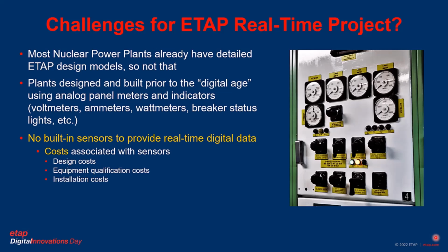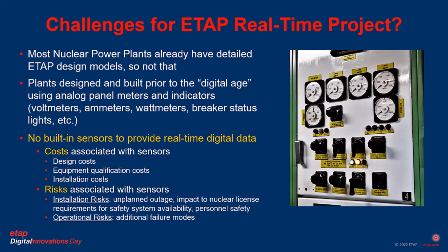There's design costs for sure, but there's also equipment qualification costs because in my industry, the equipment would have to be qualified to be installed. And then installation costs in my industry tend to be quite a bit more than in other industries. There's also risks associated with putting in the sensors that we need. For sure, there's installation risks, things like having unplanned outages. There could be impacts to the nuclear license requirements for safety system availability, and there could also be personnel safety issues, such as perhaps creating an arc flash likely situation when trying to install the equipment. There's also potential operational risks of introducing additional failure modes.